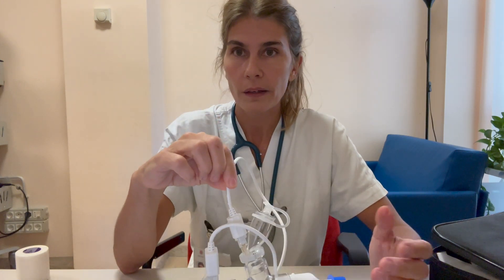In my practice, mesh nebulizers are a good option for treating COPD patients under mechanical ventilation. First, because you are not adding an additional flow to the system. With conventional jet nebulizers, an additional flow is added because jet nebulizers are activated by flow, usually compressed air. A mesh nebulizer is activated by this cable and not by flow.